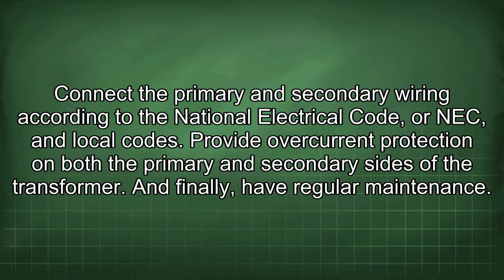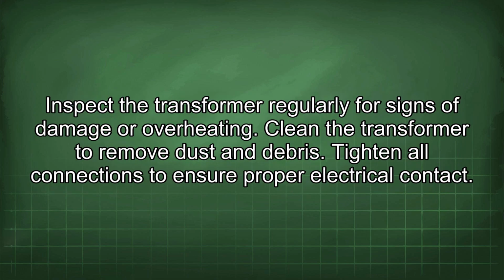Connect the primary and secondary wiring according to the National Electrical Code, or NEC, and local codes. Provide overcurrent protection on both the primary and secondary sides of the transformer. And finally, have regular maintenance. Inspect the transformer regularly for signs of damage or overheating. Clean the transformer to remove dust and debris. Tighten all connections to ensure proper electrical contact.